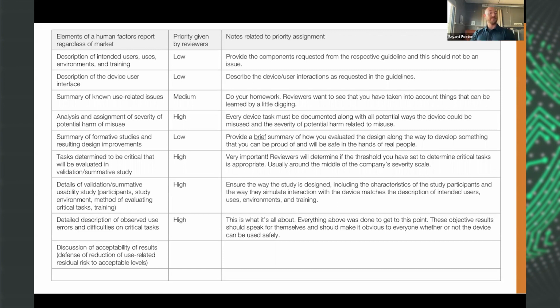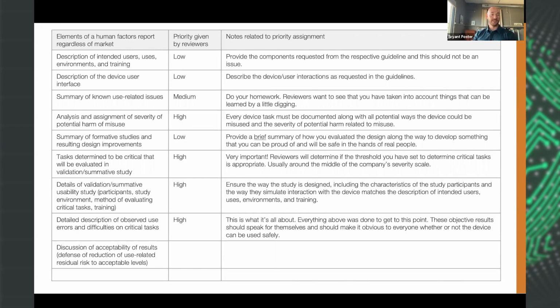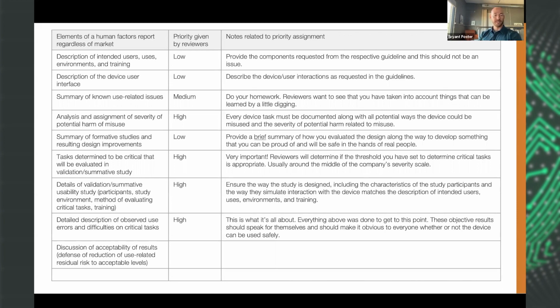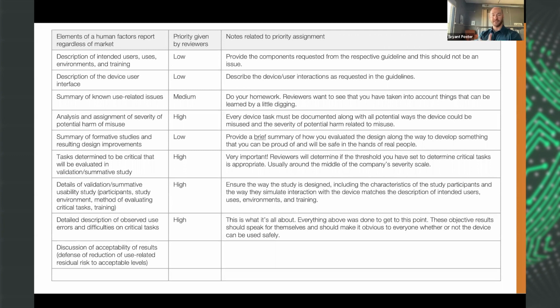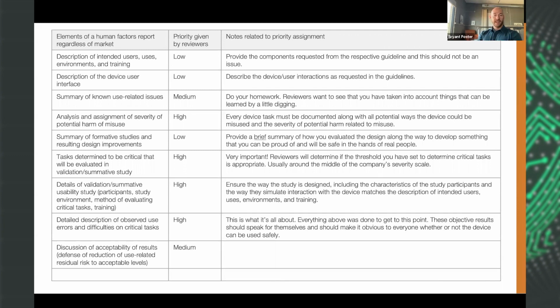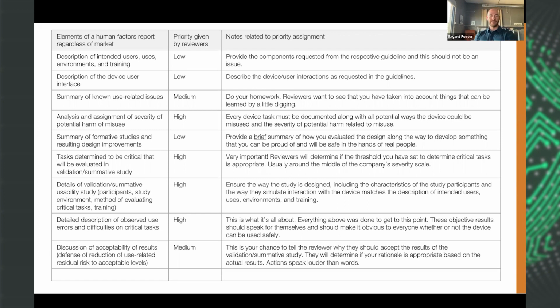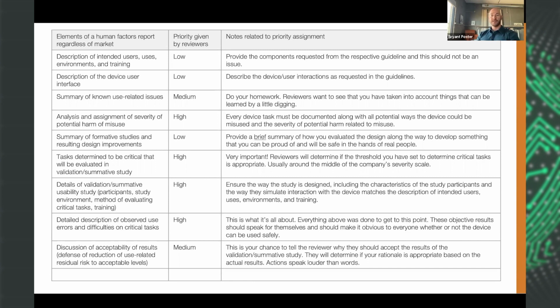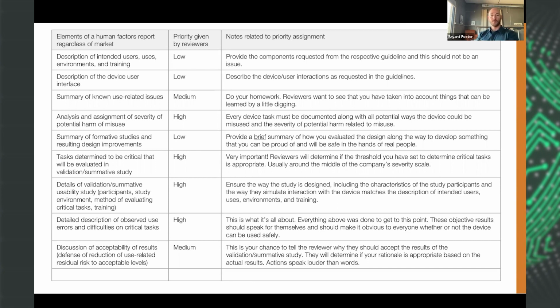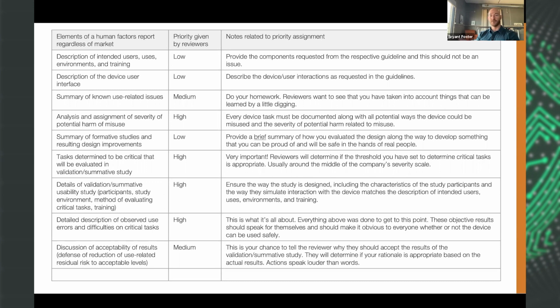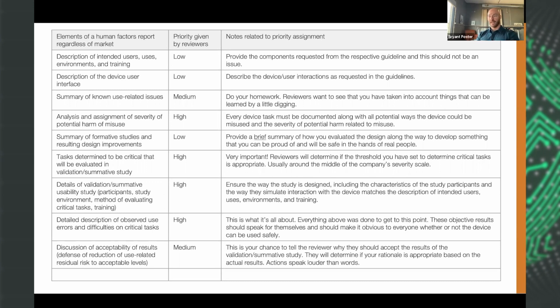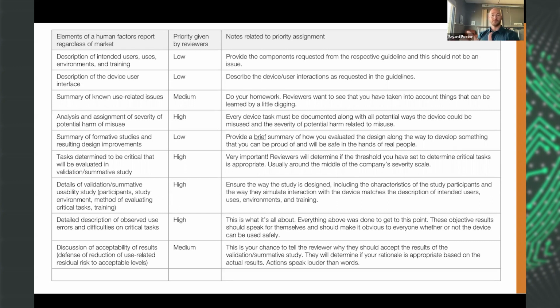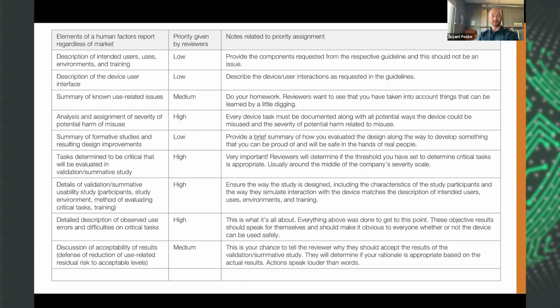In the report as well, though, you'll have a discussion of the acceptability of your results, also known as defending the reduction of use-related residual risk to acceptable levels. So you're defending that your product is safe. And I give this a medium priority. I think they're going to read it, but ultimately they're going to determine if the rationale you've written here is appropriate based on the actual results above. So the actions and the results of the study speak louder than any words you put in here about how risk has been reduced.